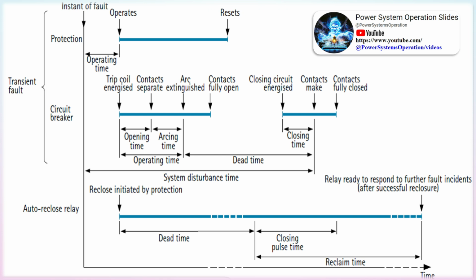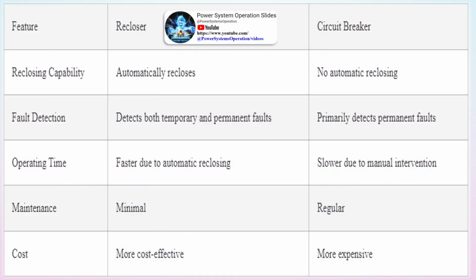These faults disappear quickly, often without any action. About 80 to 85% of line faults are transient, and a single reclosure attempt usually resolves them. Common causes include lightning, insulator flashover, swinging conductors, and temporary contact with objects.